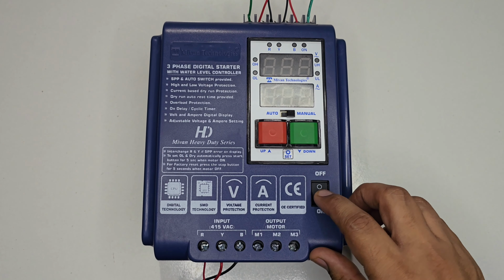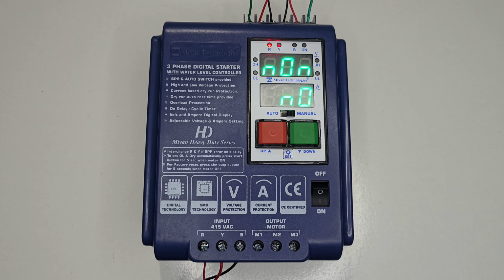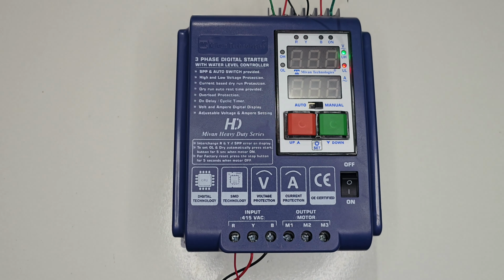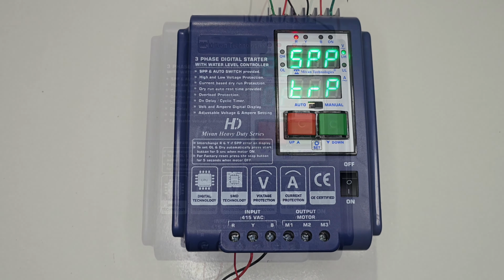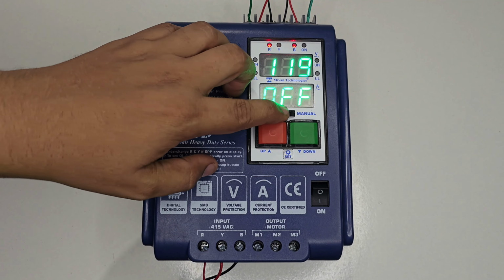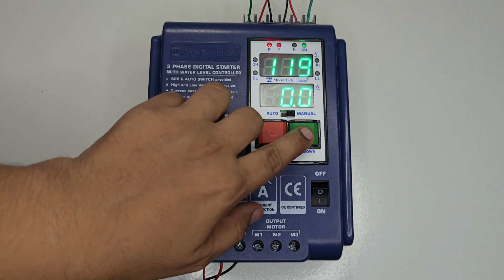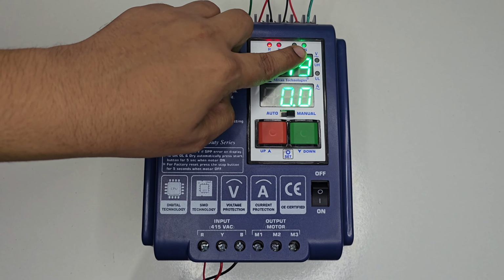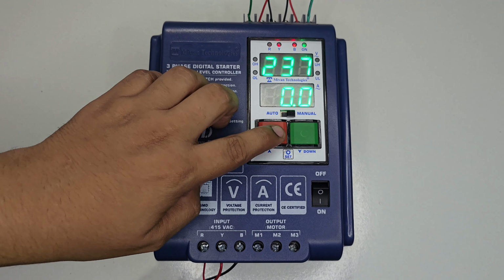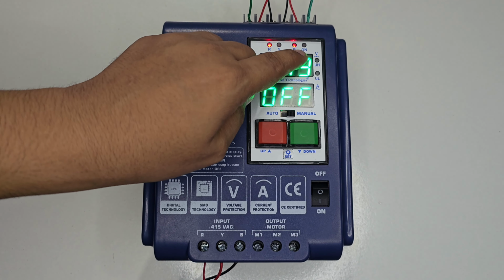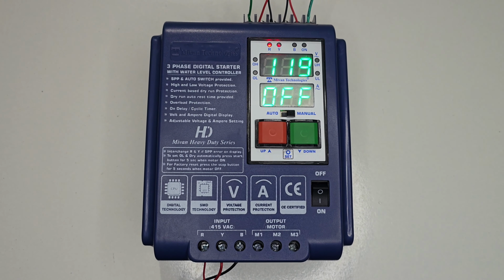Now switch on the device. If you see an SPP error, it means the phase sequence of R, Y and B is not in the correct manner. Interchange the R and Y wires at the input terminal. Put the device in manual mode. Press the start button. You can see the on indication. Press the stop button. The on indication goes. If this works, then the unit is working fine in manual mode.